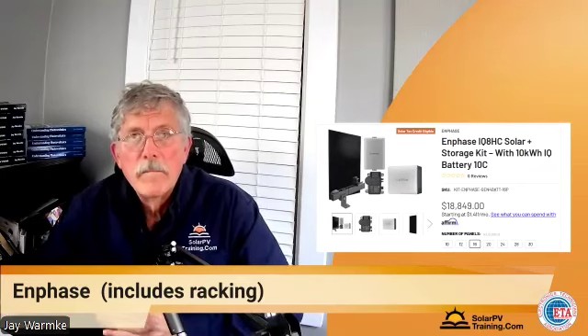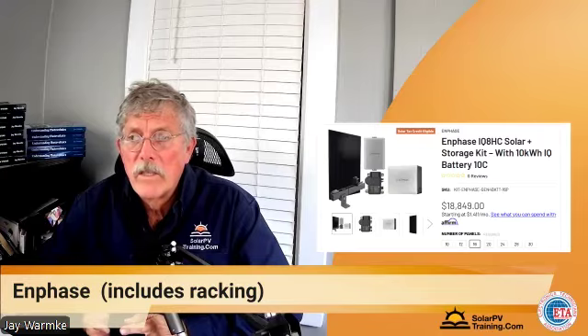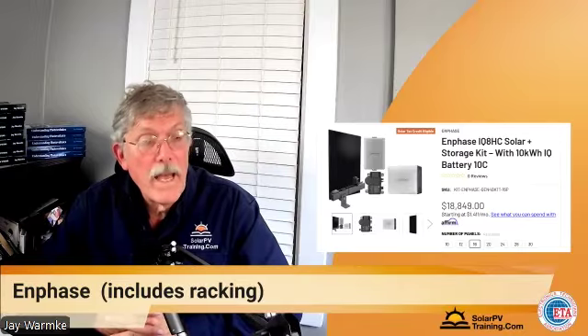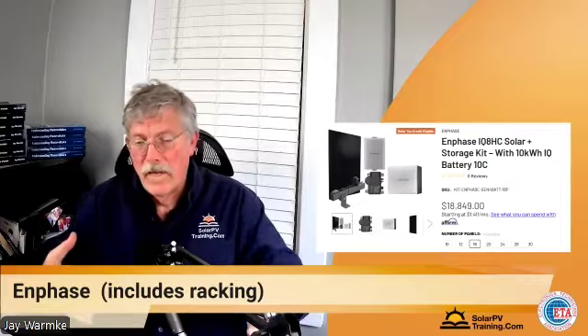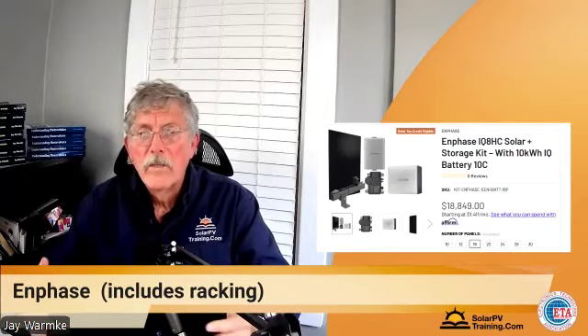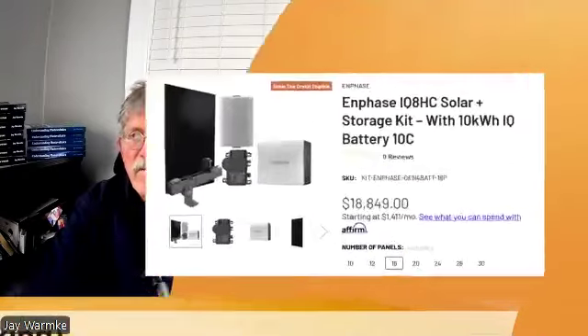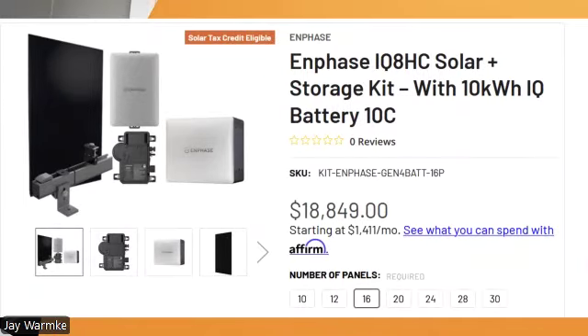Since so many people are using Enphase at the residential level, if you simply plug in a battery with their new system... because if you've ever installed or dealt with the Enphase system, the old setup had the panels, which went to a combiner box. The combiner box just combined the various branch circuits, and that went into a system controller, transfer switch, or smart switch. You hooked your generator into that smart switch, your batteries into that smart switch, and then into your service panel. So that was the brains of the outfit, and it was a pretty pricey piece of equipment.